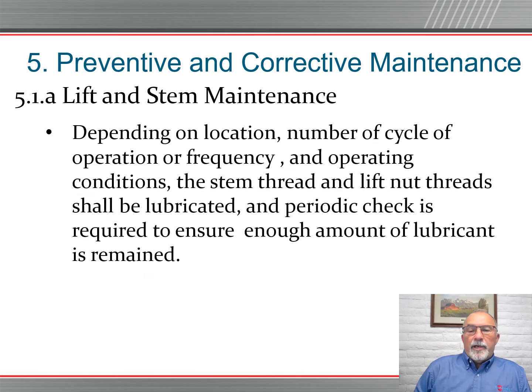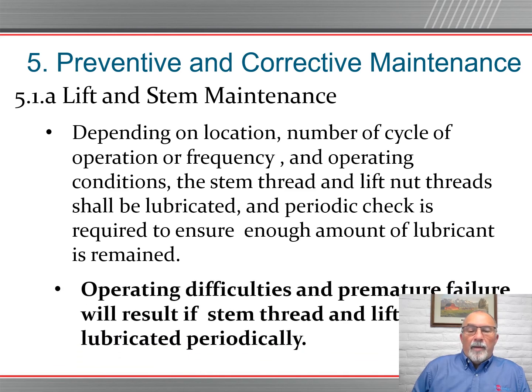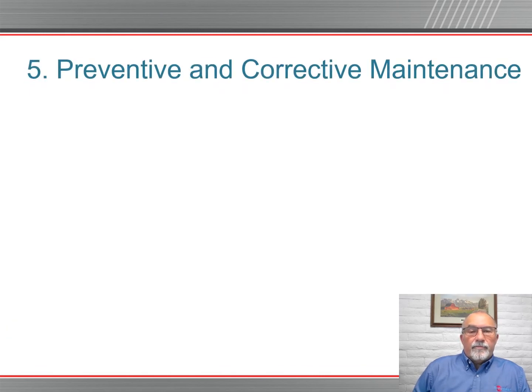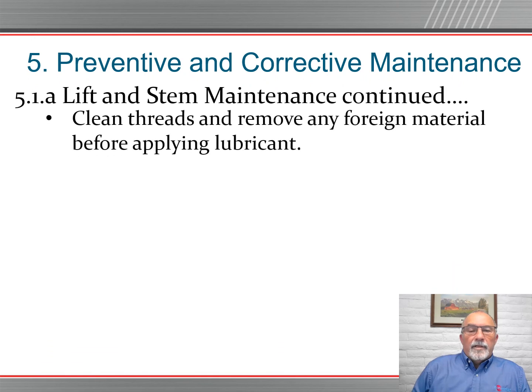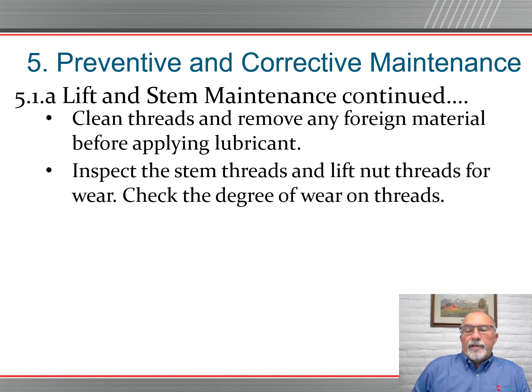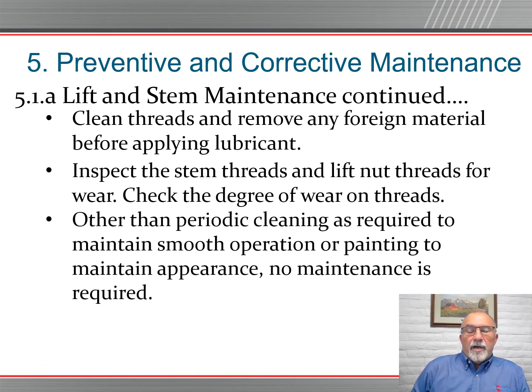Lift and stem maintenance. Depending on location, the number of cycles of operation or frequency, and operating conditions, the stem thread and lift nut thread shall be lubricated, and a periodic check is required to ensure enough lubricant remains. Operating difficulties and premature failure will result if the stem thread and lift nut are not lubricated periodically. This is very important. Clean threads and remove any foreign material before applying lubricant. Inspect the stem threads and the lift nut threads for wear.